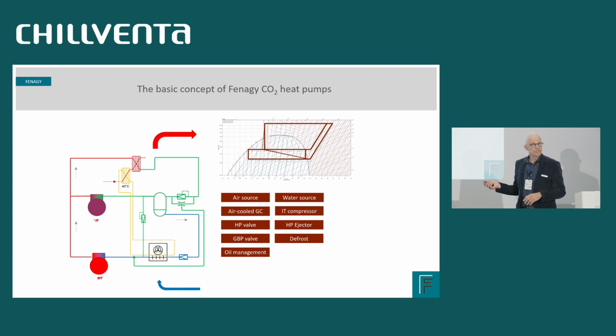In this case, we have to defrost as well. When ambient gets below 5 degrees, we have to defrost. And how do we defrost? The idea is that we take heat from the return water from the district heating grid. The return water could be 50 degrees, it could be 45, it could be 35, but we have plenty of heat available in that return water, and we are heating a glycol loop.